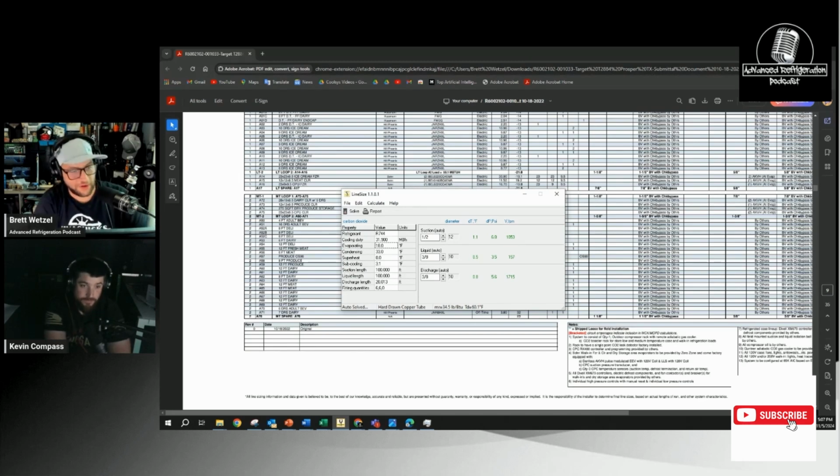I understand what you're going to say about that, but my point is just put that on the low temp, because that's what Target does. On their HFC racks, they'll put that medium temp meat box on the low temp, and it has an EPR in there. Sometimes it's not programmed right, or it just opens up to Jesus. But my point is that you could basically put in an EPR just for that one circuit and then float the whole rack up 4 or 5 degrees. That's how it should be. Like I agree with you. I'm not arguing.